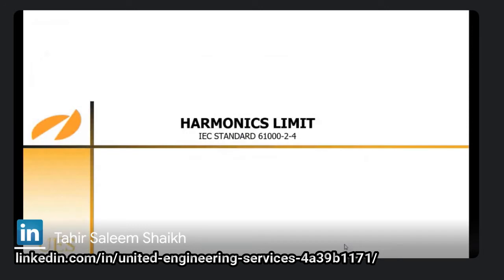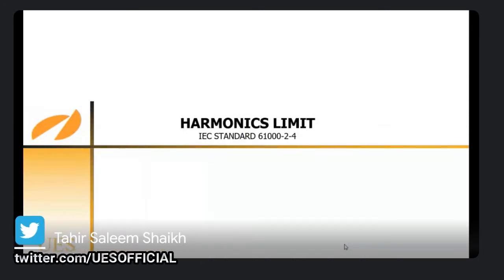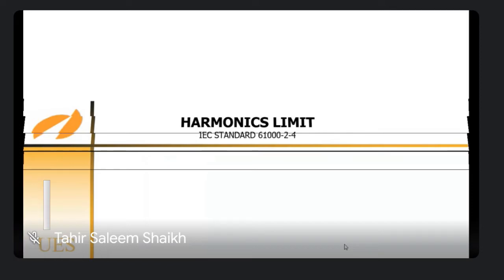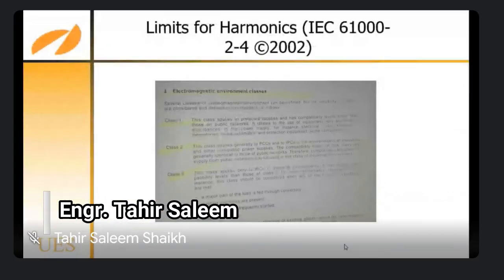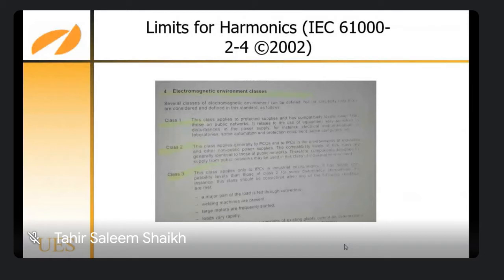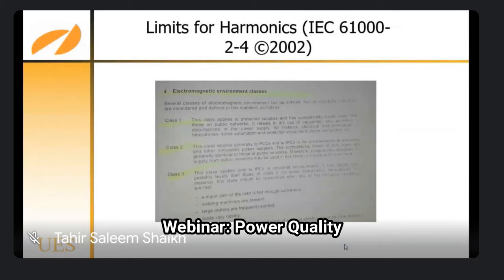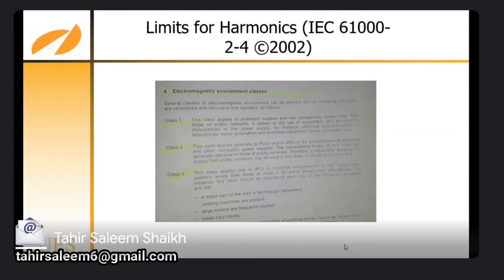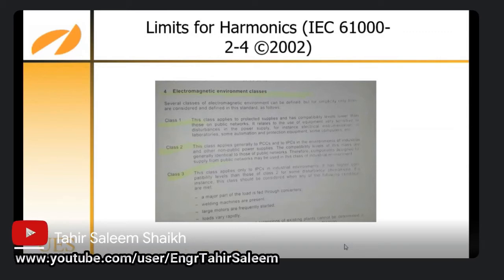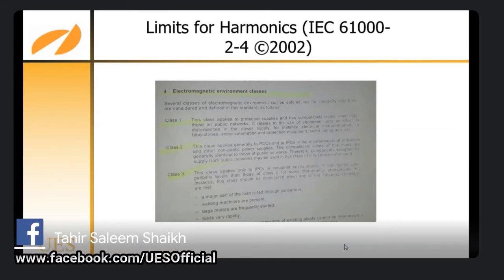Now, this is another standard harmonic limit, IEC standard 61000-2-4. This has classified into three different levels: class 1, class 2, and class 3. And I don't have a soft copy for this, that's why I give you this photograph over here. And class 1, class 2 and class 3, these are the different electromagnetic environments. And this clearly specifies that class 1 is for electronic sensitive equipment, class 2 for a different environment, and class 3 is for different requirements.